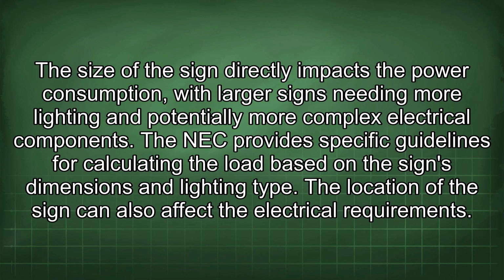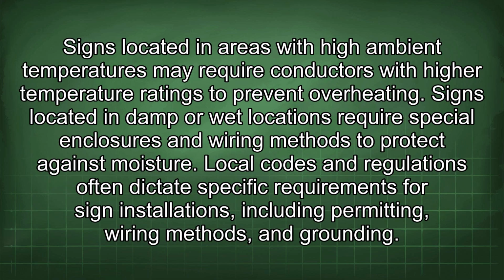The location of the sign can also affect the electrical requirements. Signs located in areas with high ambient temperatures may require conductors with higher temperature ratings to prevent overheating. Signs located in damp or wet locations require special enclosures and wiring methods to protect against moisture.